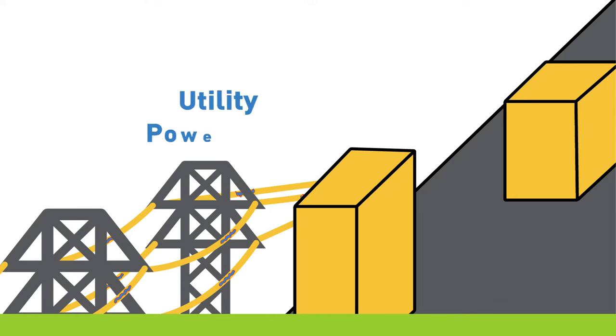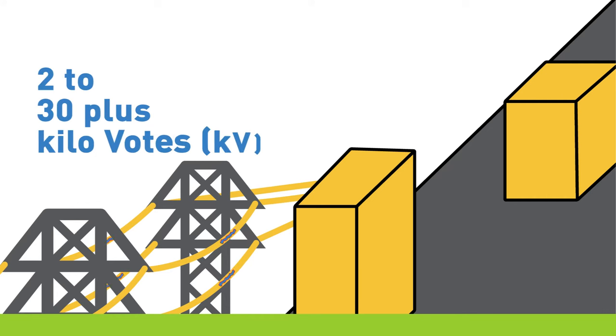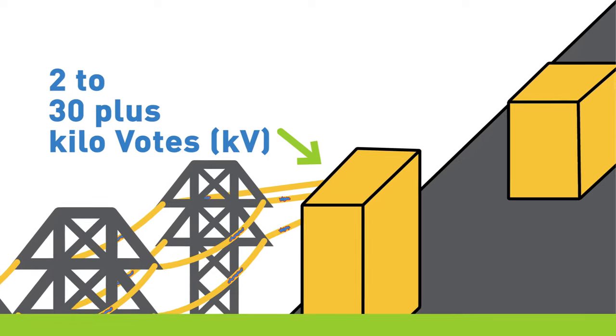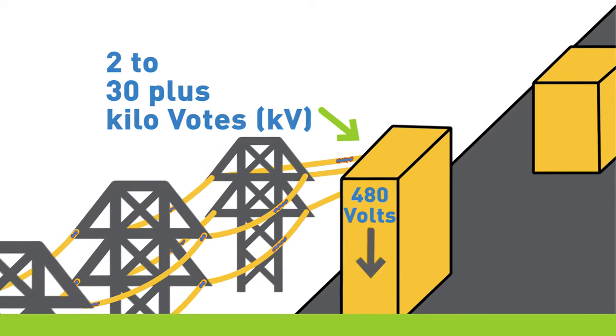We'll start with the utility feed. Power coming from the utility distribution substation can range from 2 to 30 plus kilovolts. Since the power entering the building is generally 480 volts, there has to be a transformer that can reduce the voltage down to 480 volts.